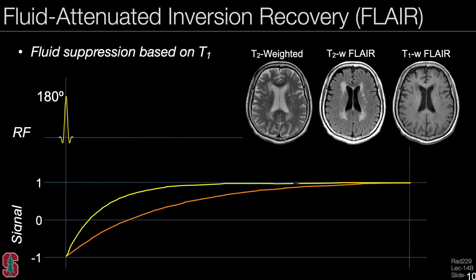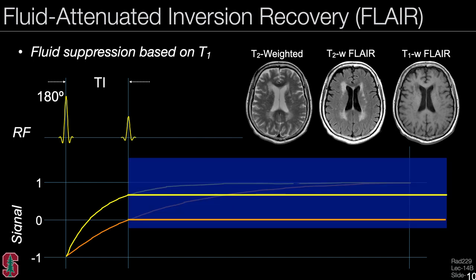Another approach with inversion recovery is called FLAIR, or fluid attenuated inversion recovery, which is fluid suppression based on T1. In the brain, we might want to suppress cerebrospinal fluid (CSF). We play an inversion pulse and use a longer inversion time to null the fluid signal shown by the orange trace, while shorter T1 signals shown by yellow are not nulled. Example images show that the bright CSF in the middle of a T2-weighted image is suppressed in FLAIR. Notably, FLAIR can be combined with both a T2-weighted sequence and a T1-weighted sequence to get different contrasts with fluid suppression.